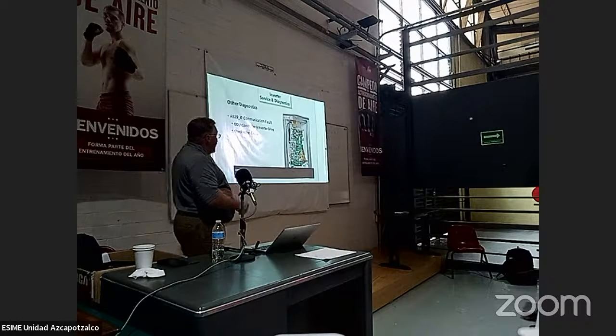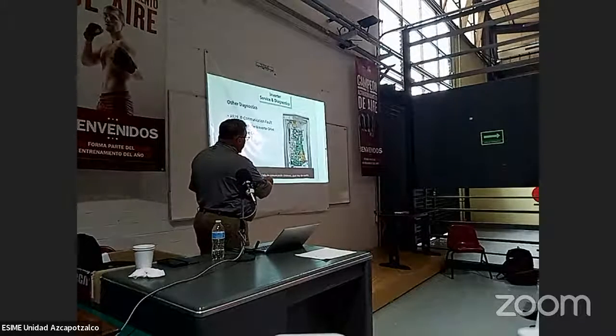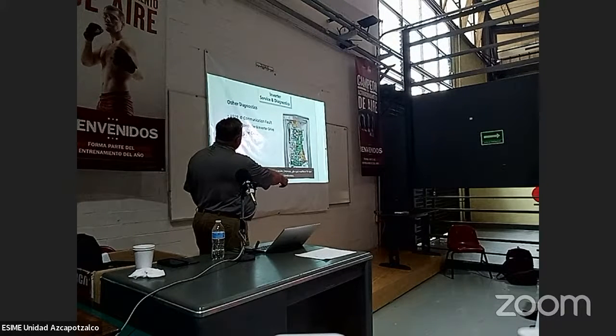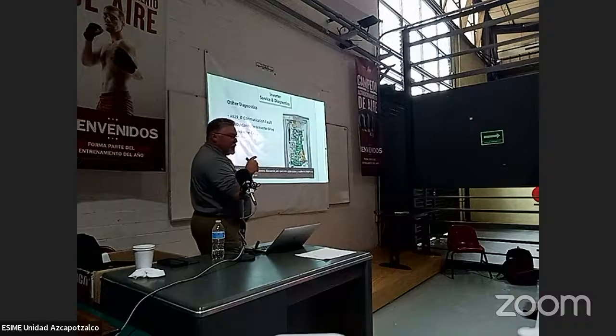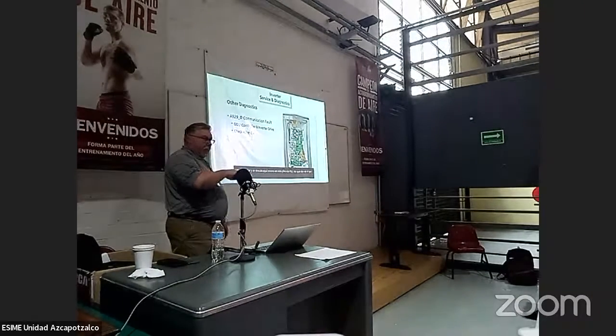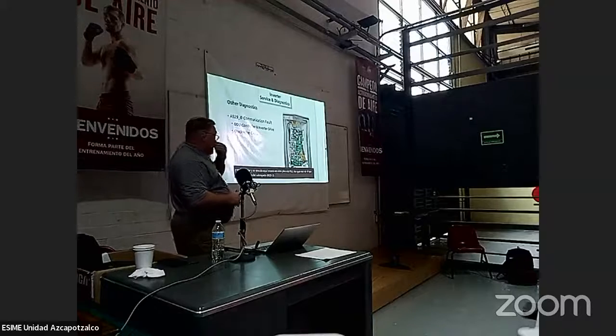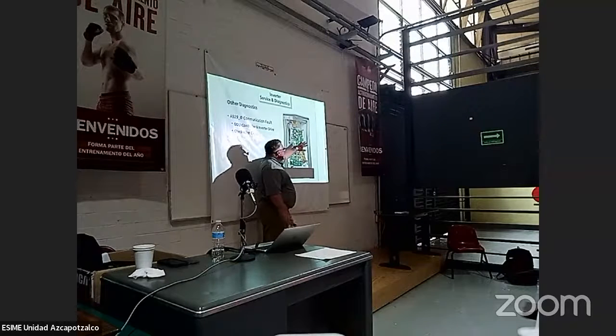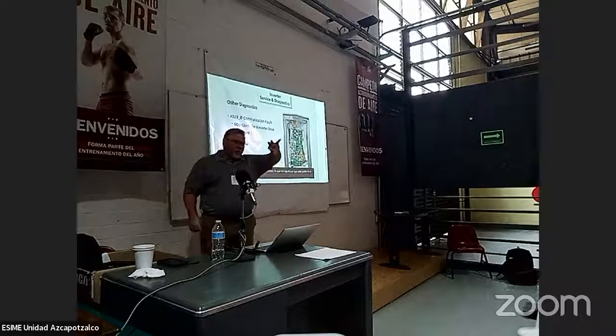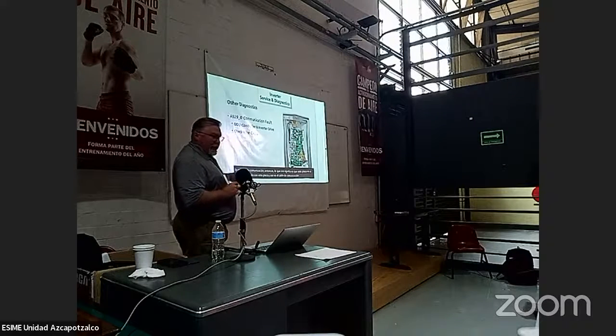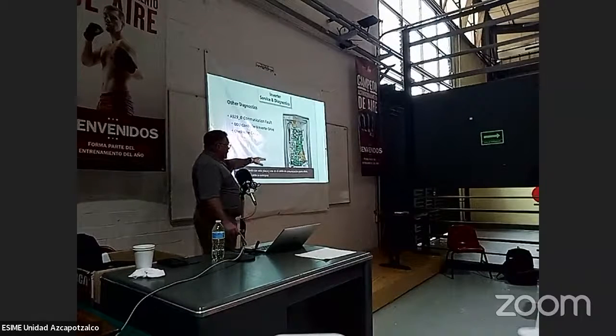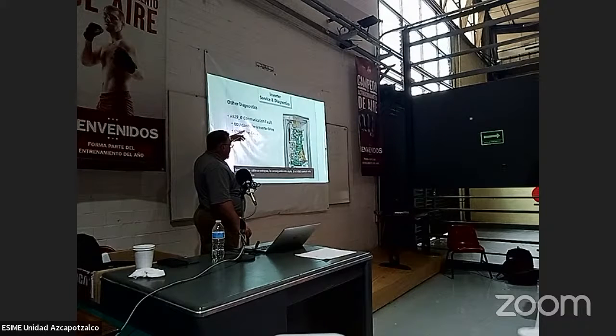A929_0 is a communication fault. So go back to what you're talking about. It's this wire right here. So this wire goes up and over, comes right back down and ties in right here on this PSO. So that's the one we're talking about, the A929_0. It is a communication fault. What that means is this board is not communicating to this board, and that's the communication cable for that. So if that cable goes bad, you'll get this fault. If the PSO board or the inverter board are bad, you'll also get this fault.